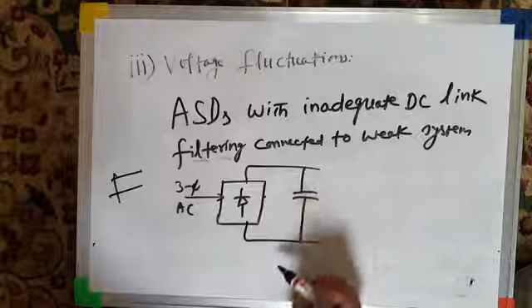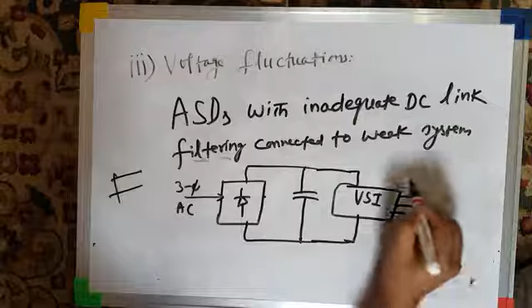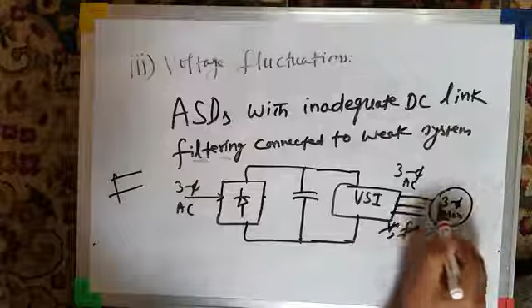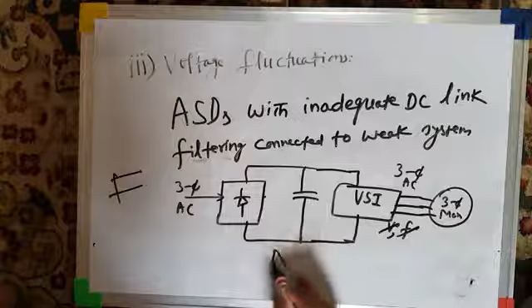Then you have an inverter, a voltage source inverter, and this voltage source inverter produces three-phase output voltages, three-phase AC, with variable voltage and variable frequency, and it is fed to a three-phase induction motor, or I should write three-phase motor. The inverter output is variable frequency, and variable frequency results in torque control and speed control of this motor. So this is the schematic diagram of an adjustable speed drive.